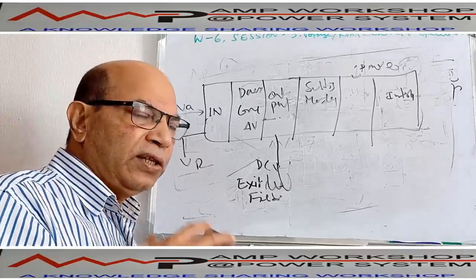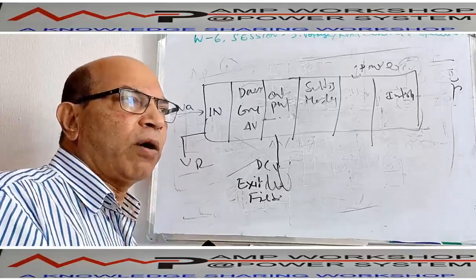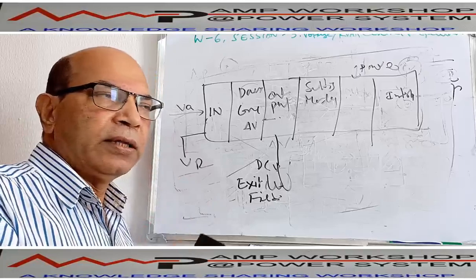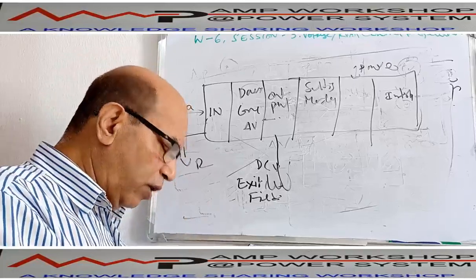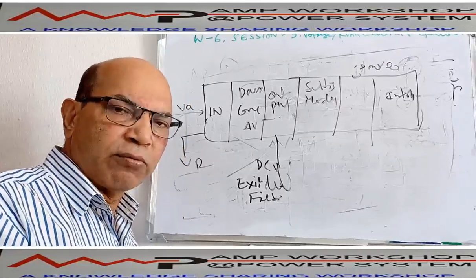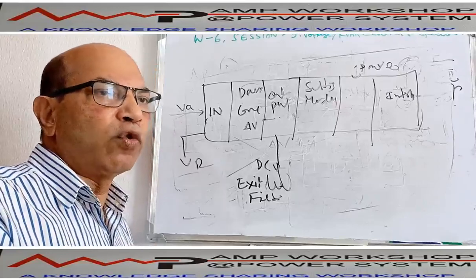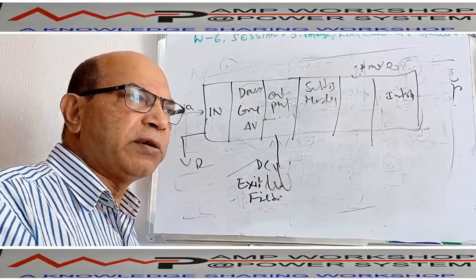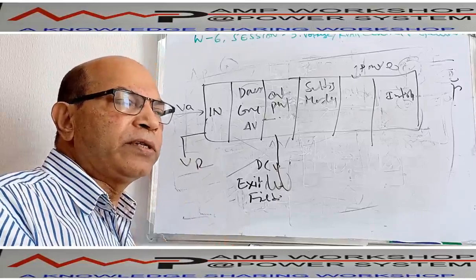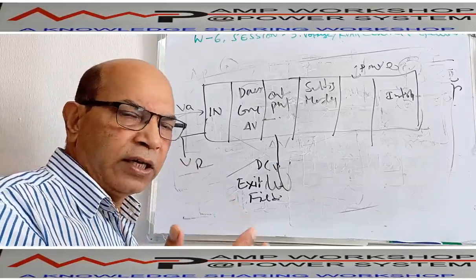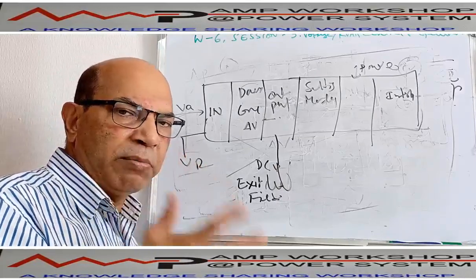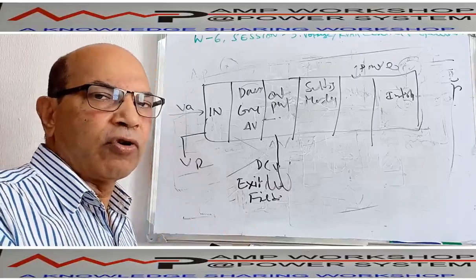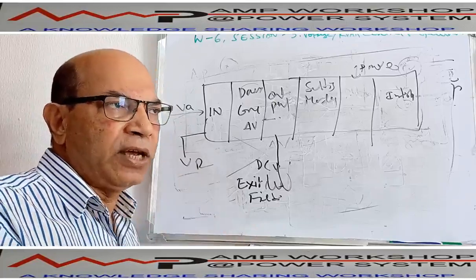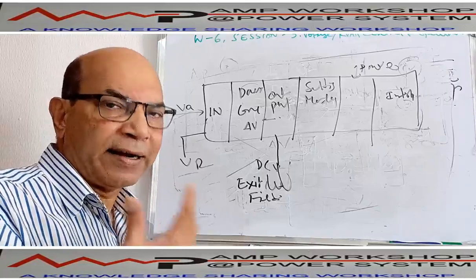Now we have to see this device's mode of operation, same like the speed controller. This device can be operated in two different modes. One mode we call isochronous voltage control mode, another is droop voltage control mode. As we said, in the case of speed, isochronous mode means it will run with a constant frequency. You cannot change the frequency. Frequency will be maintained. And there is another mode we call droop mode, where frequency will change as per the load, as per the active power.